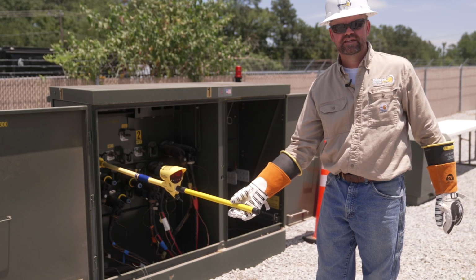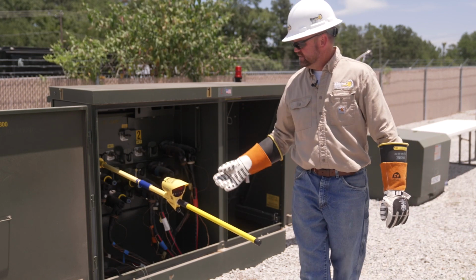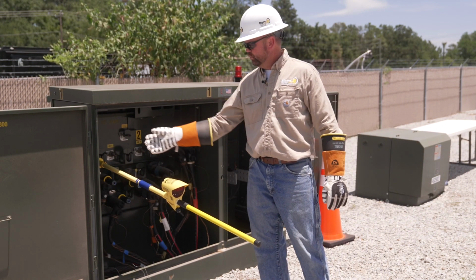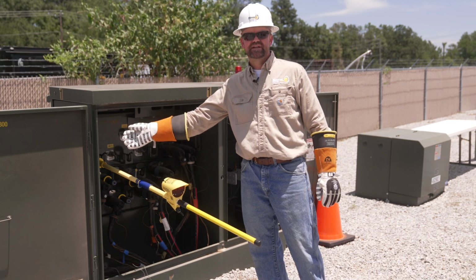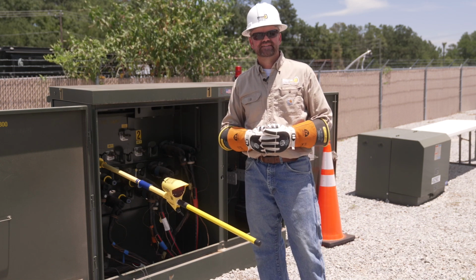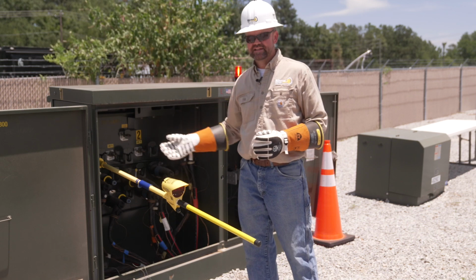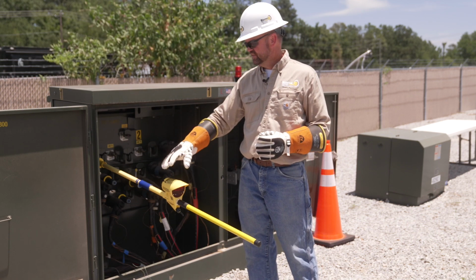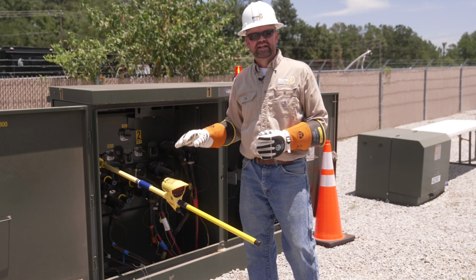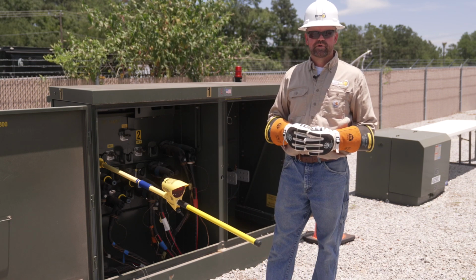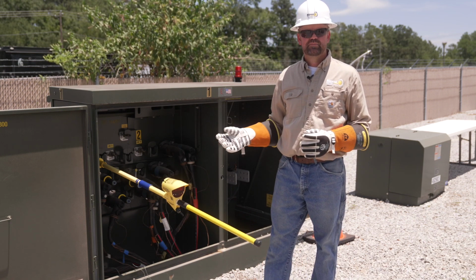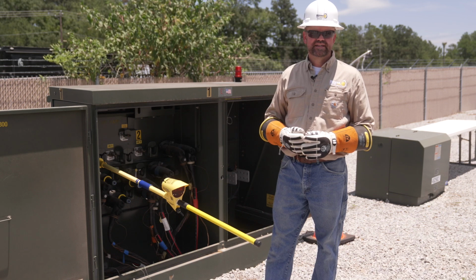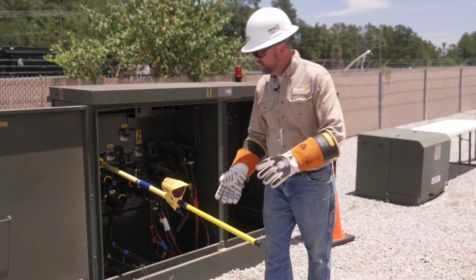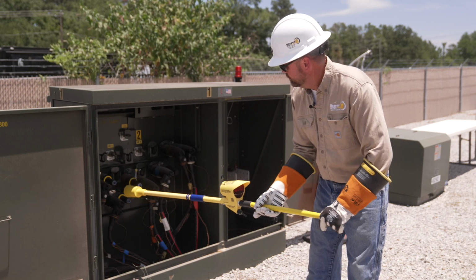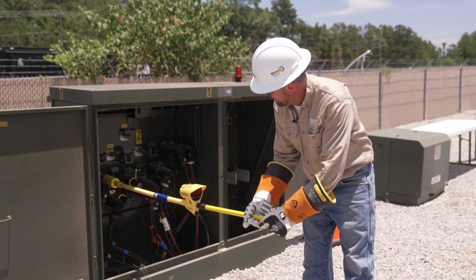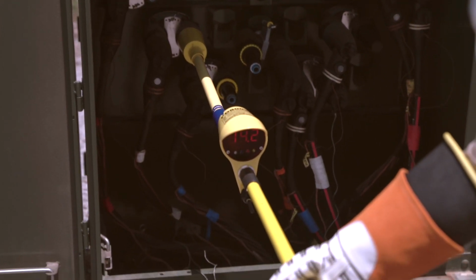This is 14 kV. So what I've done is I've removed this housing away from this ground plane close to the cabinet here. So I've basically done two things. I've made this work method a lot safer simply by removing this housing close to the ground, and on top of that, I've made this reading much more accurate. Instead of reading 17.2 kV, I'm reading 14 kV. So I can go ahead and check my other phases as well. Even though they weren't as close to the cabinet, the reading should be more accurate, and they are.